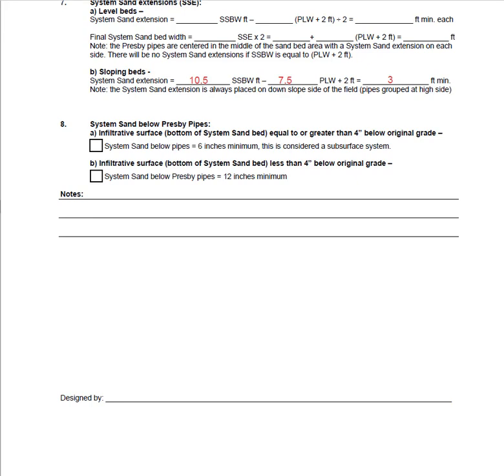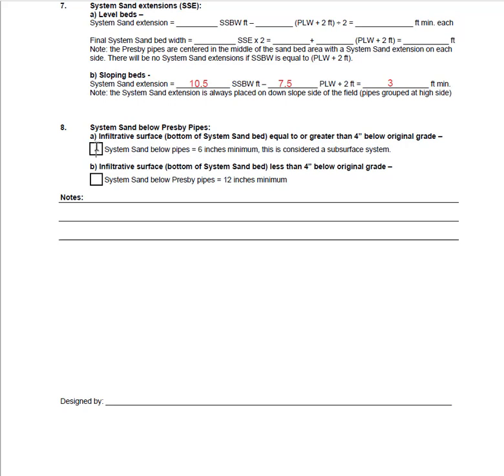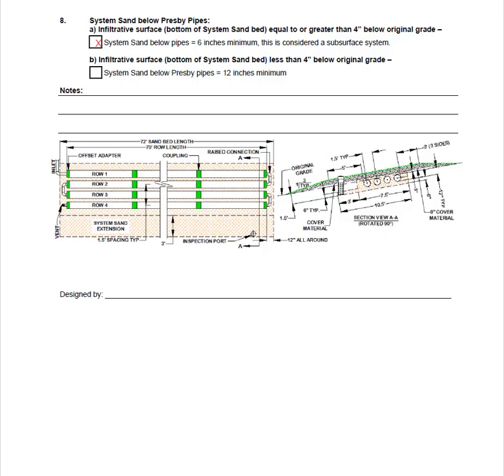The last step, step eight, helps us determine how much sand will be required beneath the pipes. If the bottom of the system sand bed is greater than four inches below grade, the system is considered a subsurface system and only needs six inches of sand beneath the pipes. If the bottom of the sand bed is less than four inches below grade, it is considered an elevated system and will require 12 inches of sand beneath the pipes. For our example, our system was a subsurface system. Any additional information you want to include about your system design can be added in the notes section at the bottom of the worksheet. A drawing of the design we just completed is also included, which can be found in your design and installation manual under example number two.